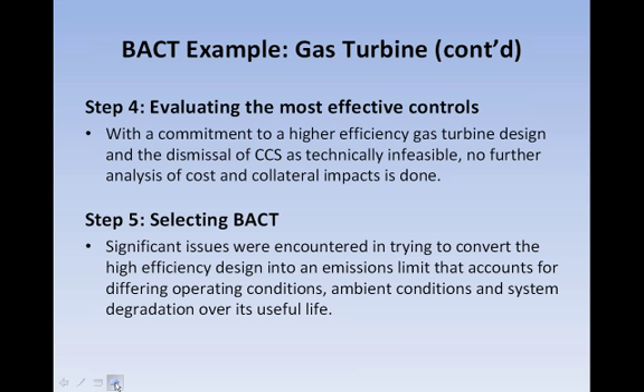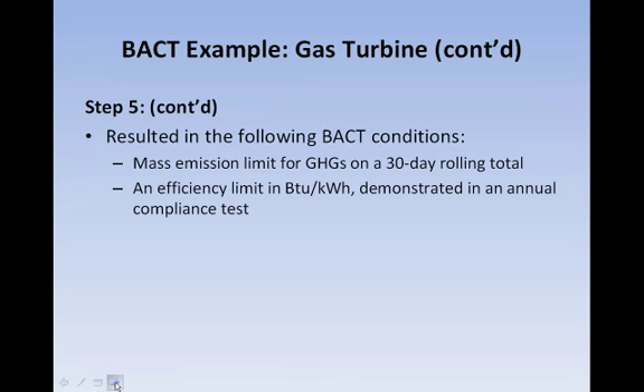Thus, we move on to step 5. The agency approved the higher efficiency design but had difficulty trying to convert the high efficiency design to an emissions limit that would apply at all times and that would account for differing operating conditions, ambient conditions, and system degradation over its useful life. Thus, the permit conditions were as follows: emission limits for CO2e based on a 30-day rolling total, and an efficiency limit in BTU per kilowatt hour demonstrated in an annual compliance test.